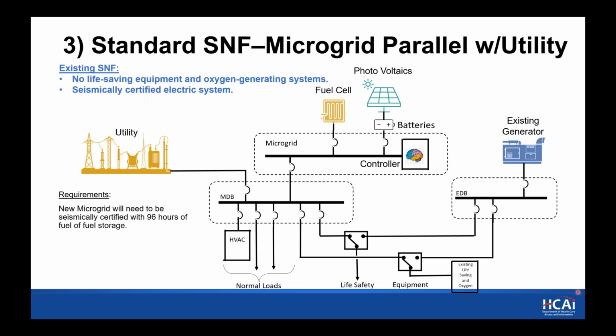I'm not going to go into detail of whether it's subacute or not. They're basically the same solution. In this case, you're backing up the entire facility. So by virtue of backing up the entire facility, you do get the backup of all of your cooling loads without having to transfer loads. And you do get backup of any life-saving and oxygen equipment, as those are circuited in the system already.